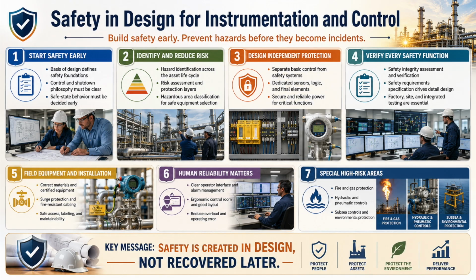Do not accept fail-safe as a label without analysis. Closing a valve may be safe for one scenario and dangerous for another. Holding the last position may preserve stability or trap hazardous energy. Opening a valve may depressurize equipment or feed a fire. The correct failure action comes from process analysis, not habit.